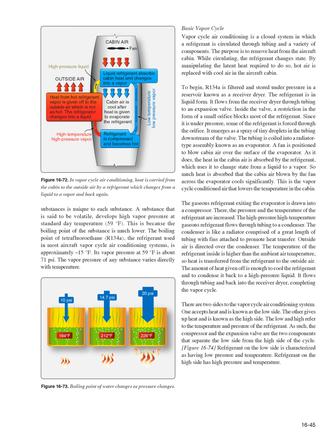So much heat is absorbed that the cabin air blown by the fan across the evaporator cools significantly. This is the vapor cycle conditioned air that lowers the temperature in the cabin. The gaseous refrigerant exiting the evaporator is drawn into a compressor. There, the pressure and the temperature of the refrigerant are increased.